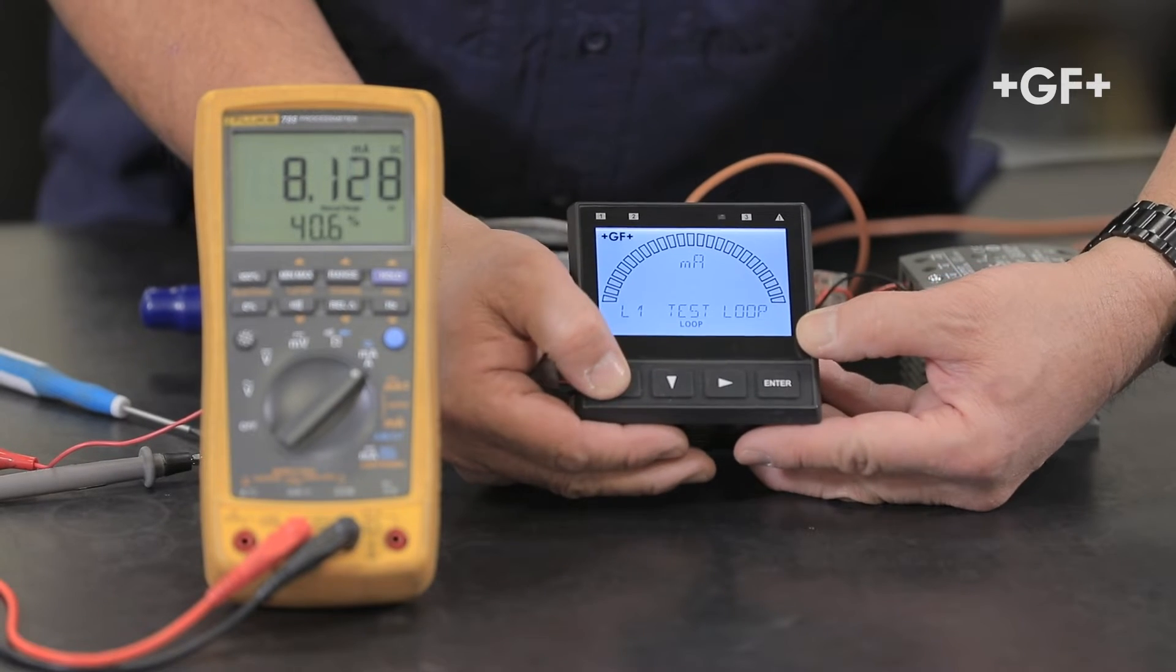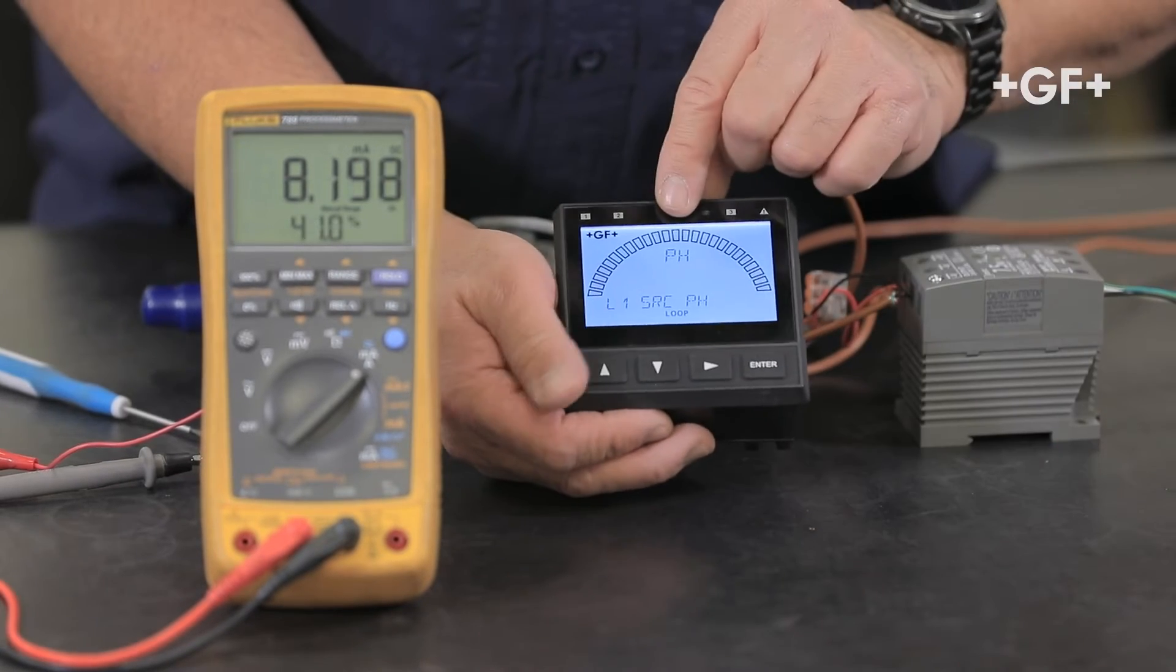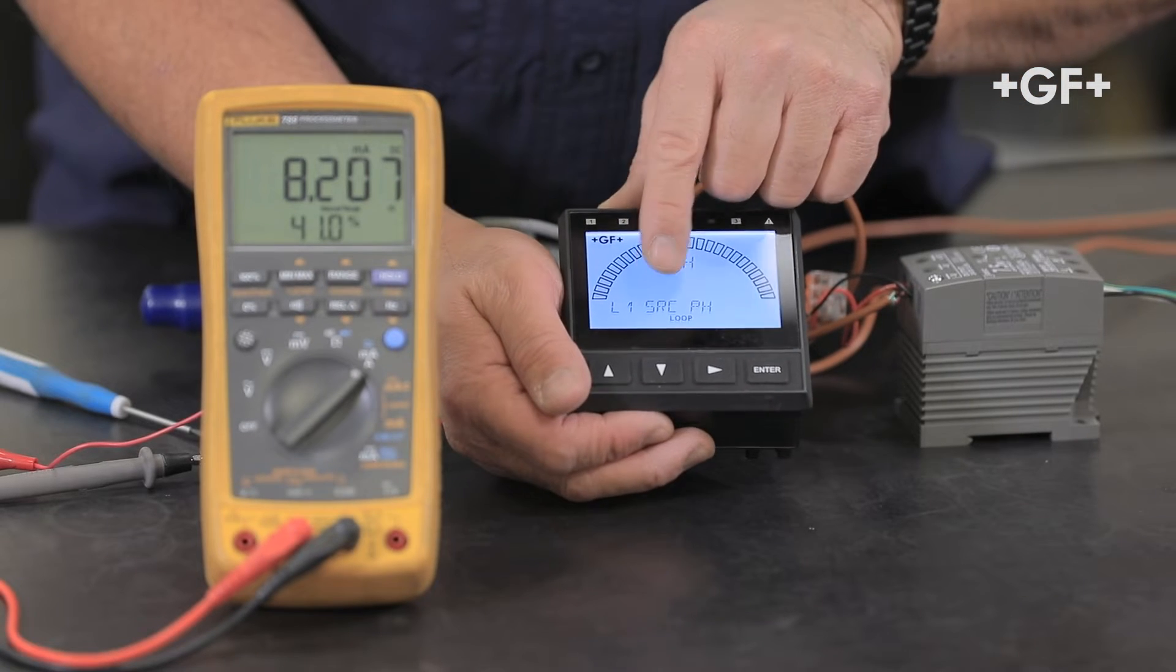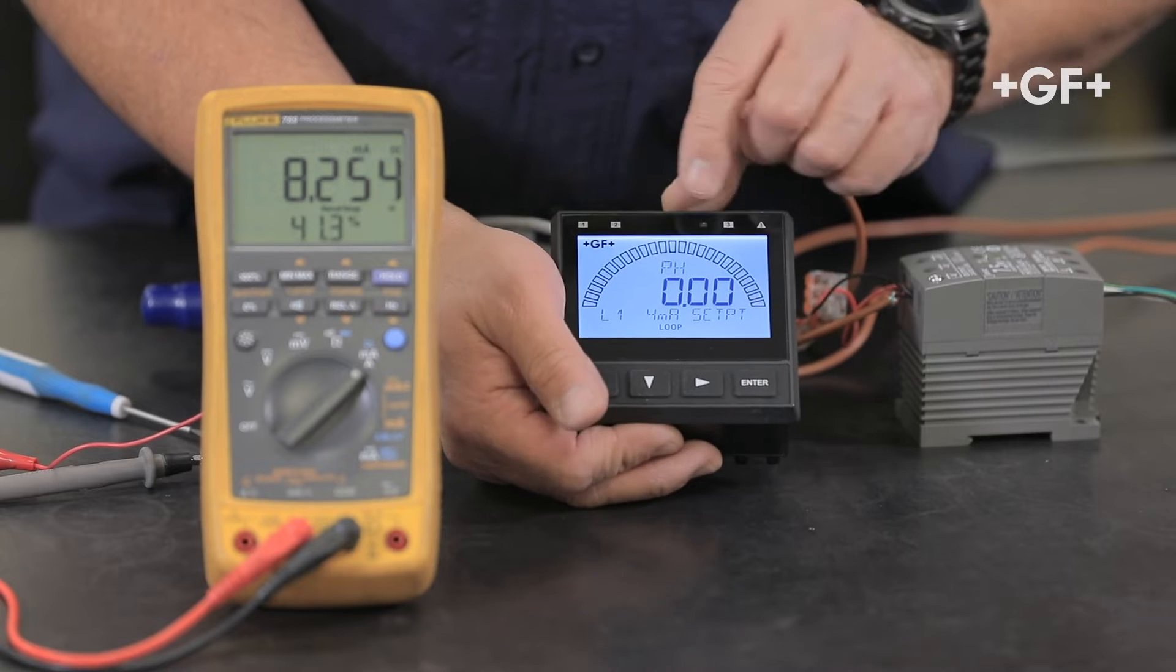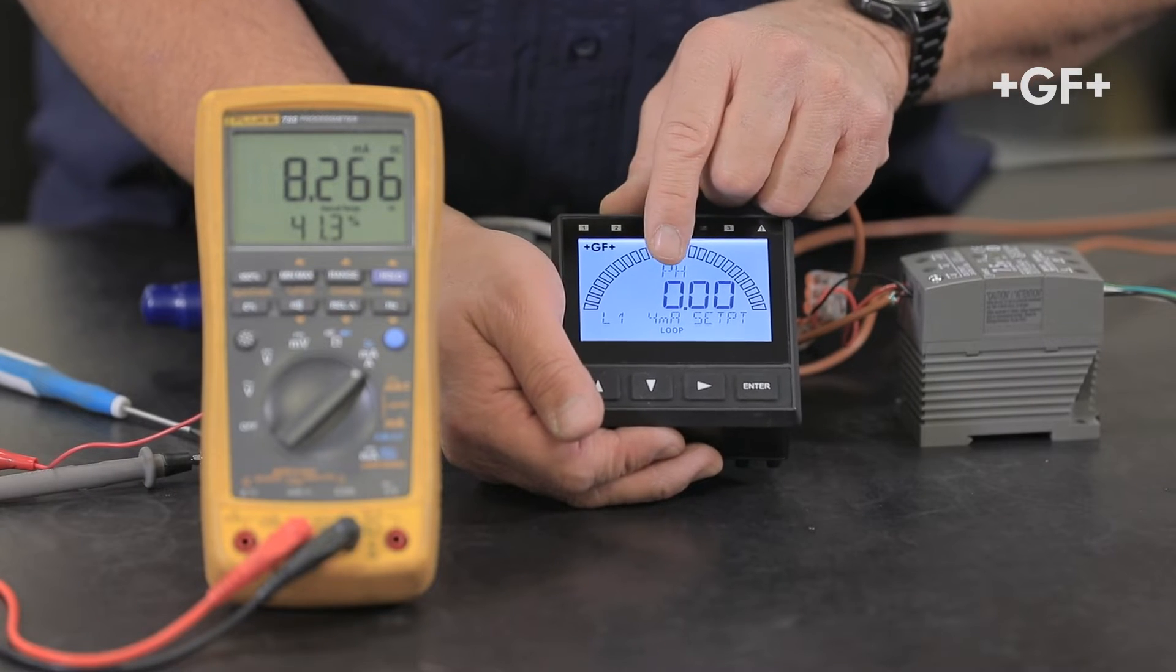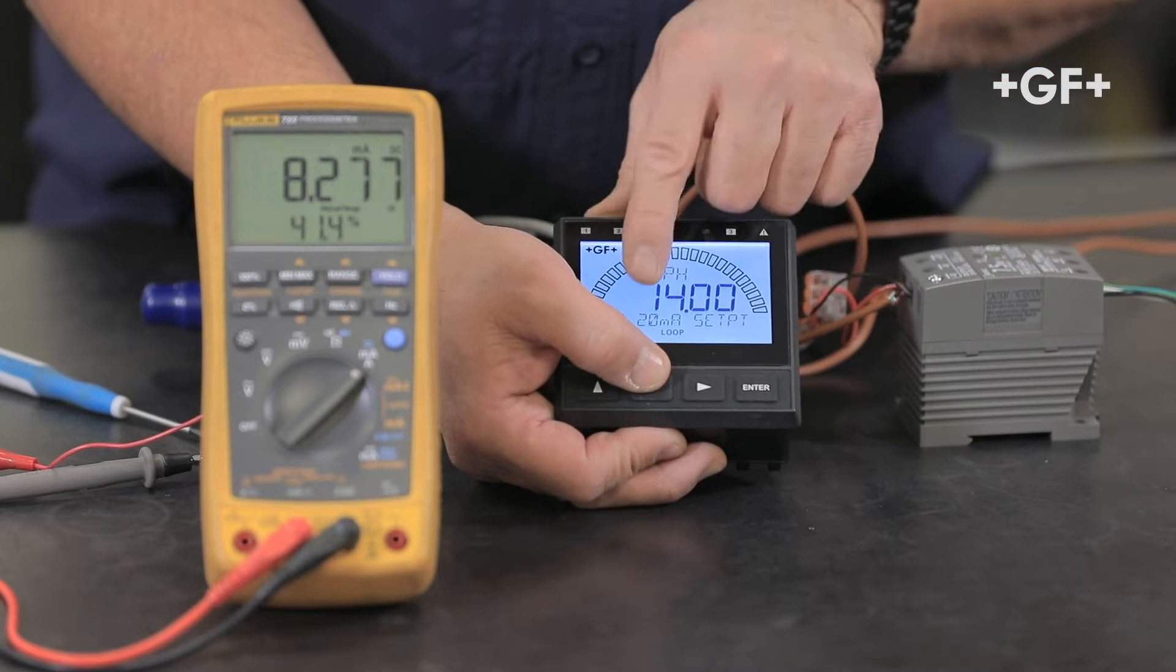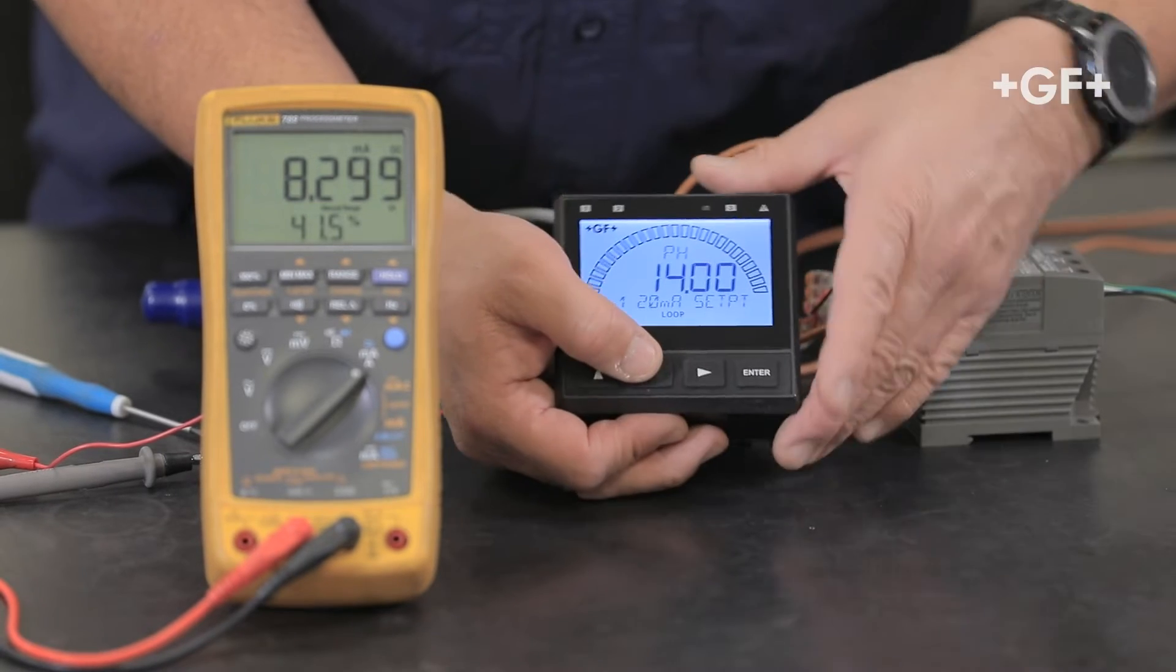I'm going to up arrow. This is the source. L1 source is for pH. Good. Down arrow. L1 4 milliamp set point is zero, 20 milliamp set point is 14. Perfect.